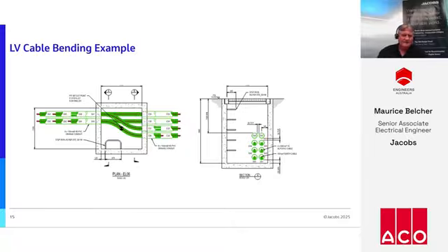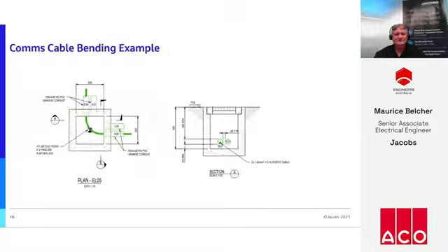Moving on, this is an LV example, and I like how our modelers and designers used colour to differentiate between the HV and LV services. You can see how we've labelled each conduit and pit, and there are key schedules documenting which cables go in each conduit, so installers know which conduits are spare, which cables are expected, and that we've accounted for all the bends. The key takeaway is that as cables get smaller, the pits get smaller and the bending radius is slightly less.